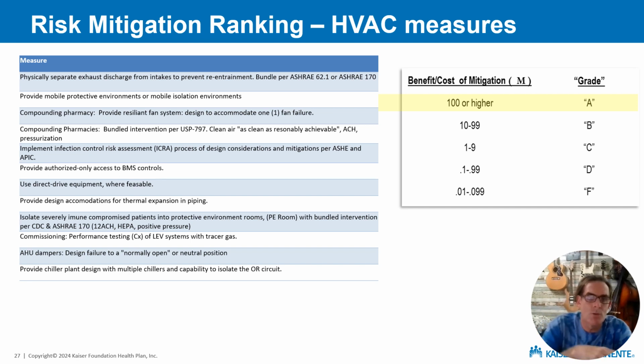You see several risks associated with compounding pharmacies. That's because the cost of the medication that we're dealing with in those pharmacies is so large that they immediately move that numerator into the $10 million losses or $100 million losses. So the risk mitigations that we do in that environment can be quite effective. Rounding out the list here are some very simple measures: direct drive equipment, thermal expansion, commissioning, normally open failures, providing 2 chillers rather than just 1, things like that.